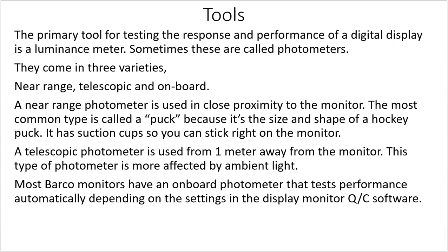A telescopic photometer is used from one meter away from the monitor. This type is more affected by ambient light, but it's also better at accounting for ambient light. Most Barco monitors have an onboard photometer that tests performance automatically, depending on the settings in the display monitor quality control software.